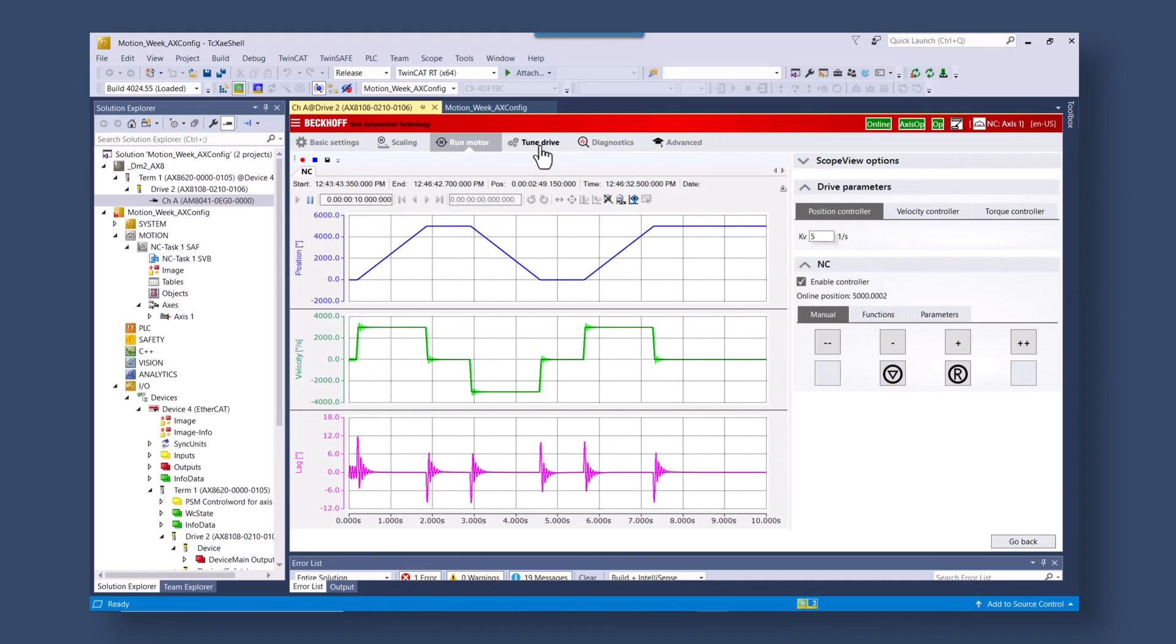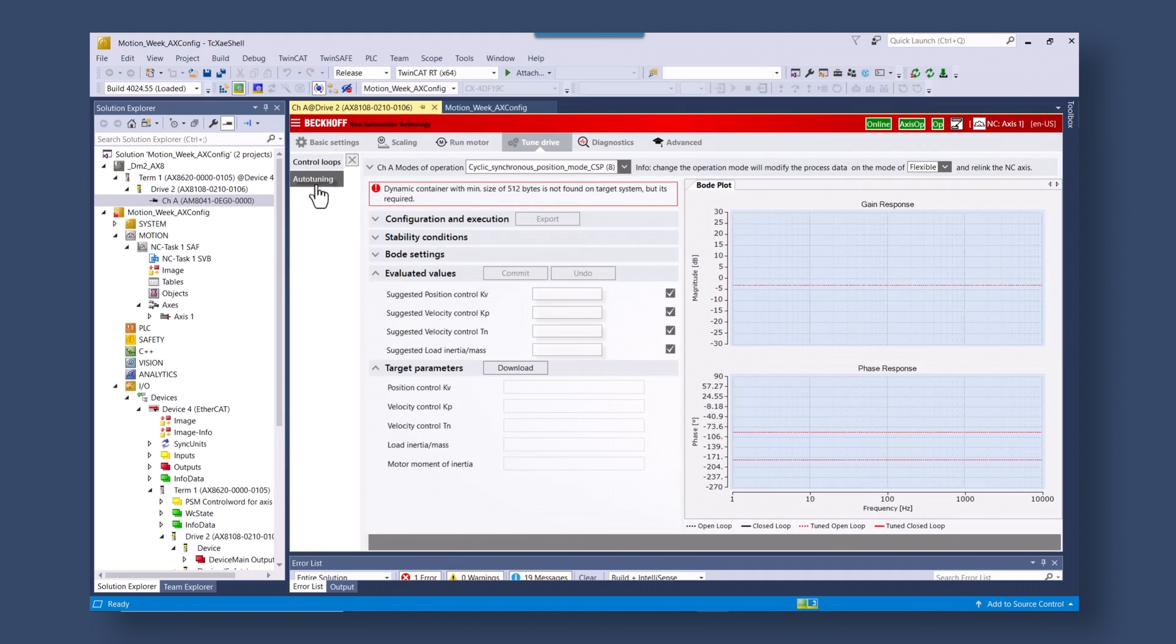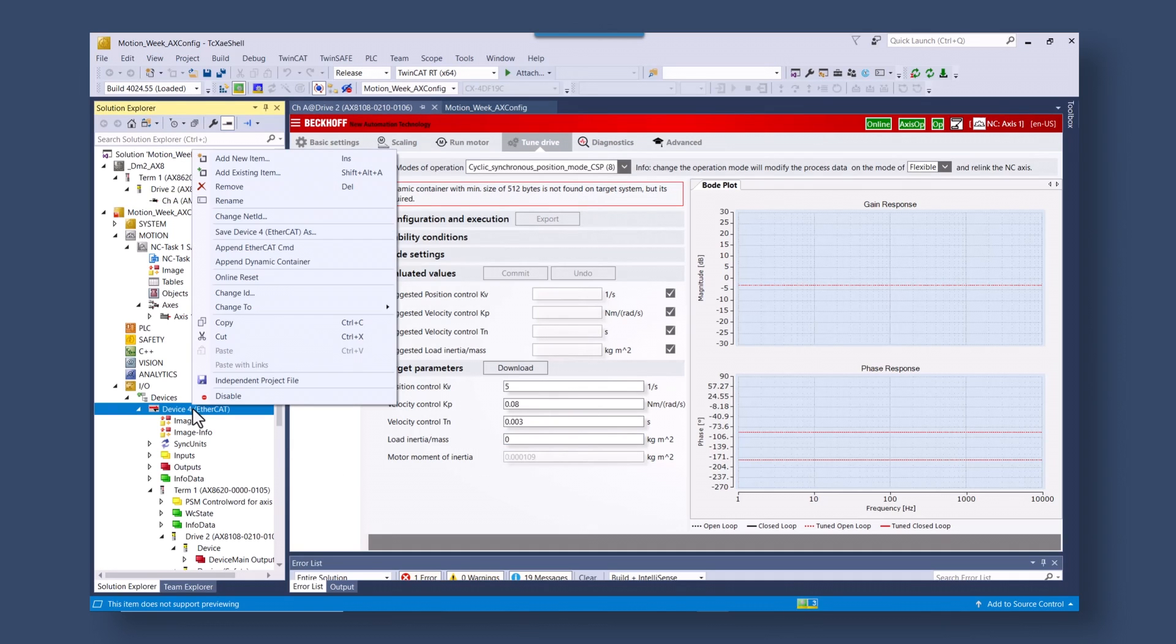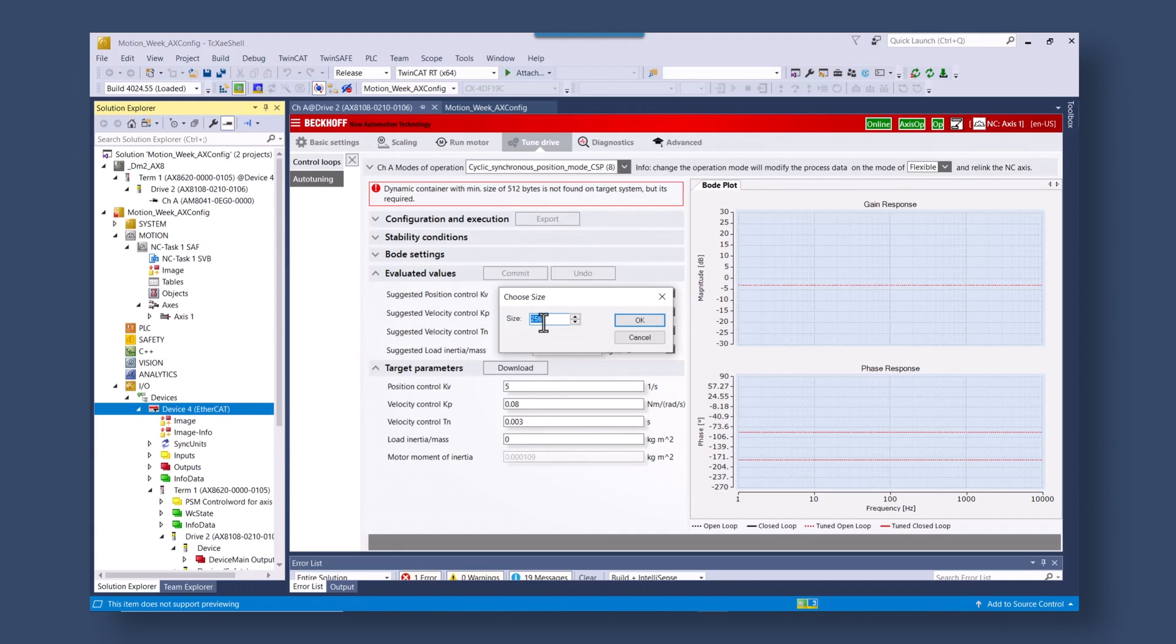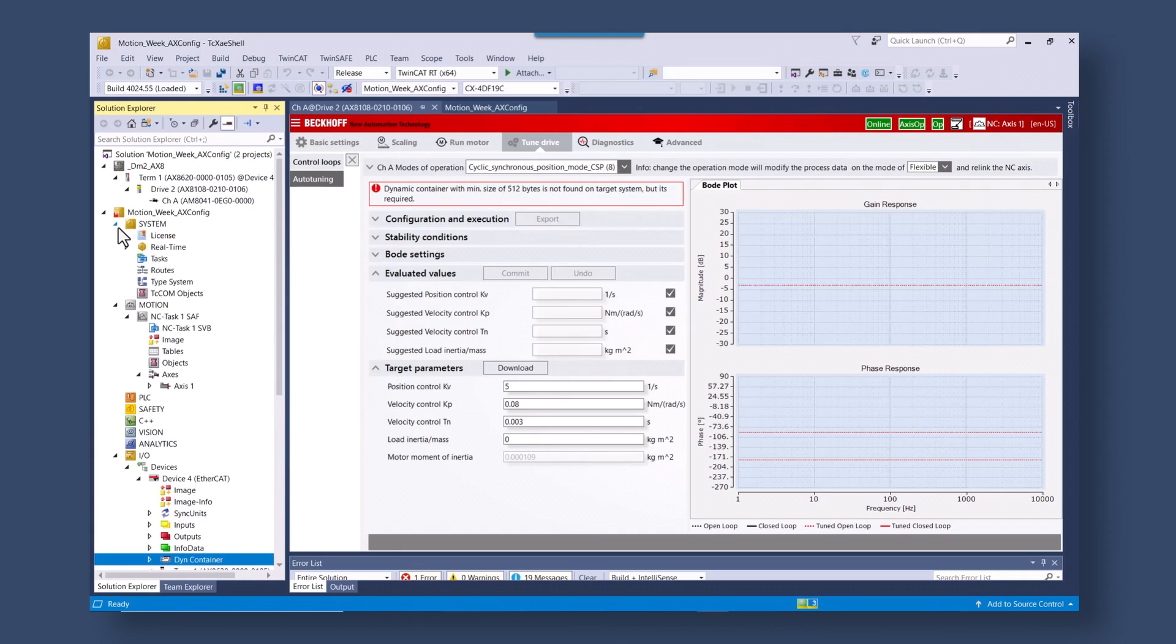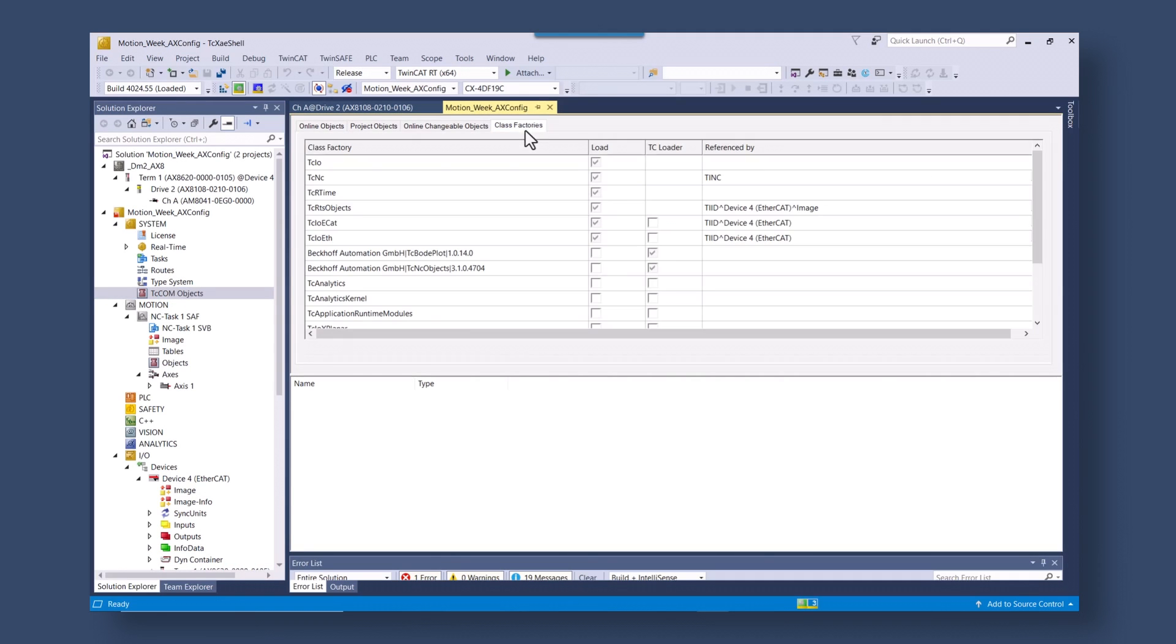Go to the drive manager tune drive section. Go to auto tuning. In here you can start seeing the auto tuning interface. The very first step we're going to do is add a dynamic container and we're going to set it for over sampling. We're going to enable the bode plot and the over sampling for the NC by these two checkboxes.